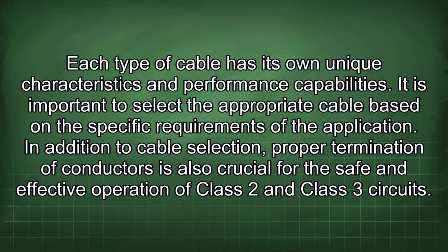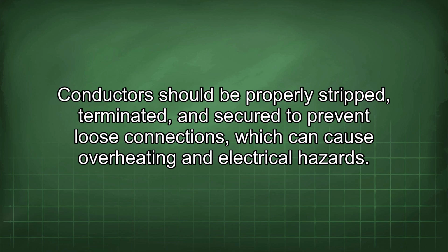It is important to select the appropriate cable based on the specific requirements of the application. In addition to cable selection, proper termination of conductors is also crucial for the safe and effective operation of Class 2 and Class 3 circuits. Conductors should be properly stripped, terminated, and secured to prevent loose connections, which can cause overheating and electrical hazards.